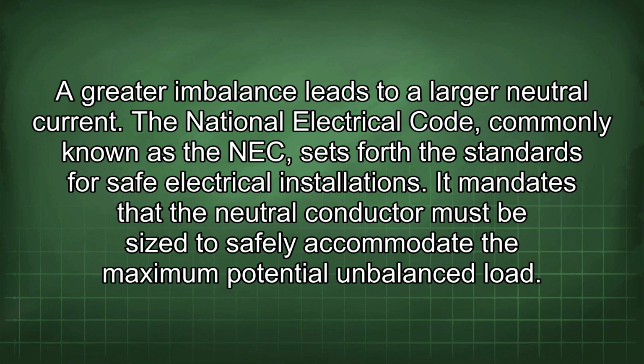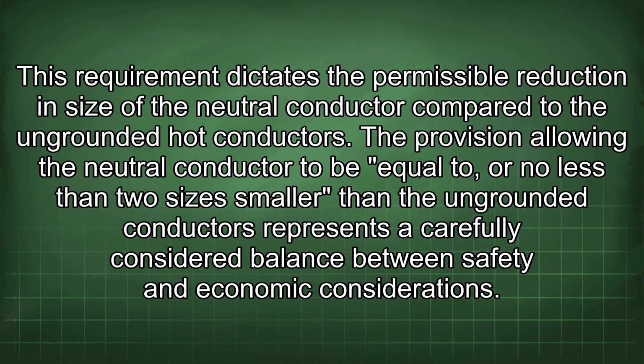The National Electrical Code, commonly known as the NEC, sets forth the standards for safe electrical installations. It mandates that the neutral conductor must be sized to safely accommodate the maximum potential unbalanced load. This requirement dictates the permissible reduction in size of the neutral conductor compared to the ungrounded hot conductors. The provision allowing the neutral conductor to be equal to, or no less than 2 sizes smaller than the ungrounded conductors represents a carefully considered balance between safety and economic considerations.